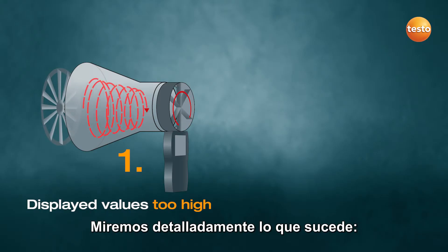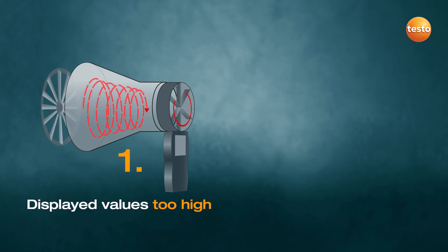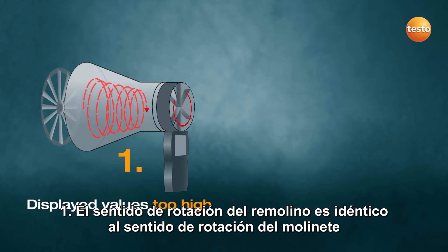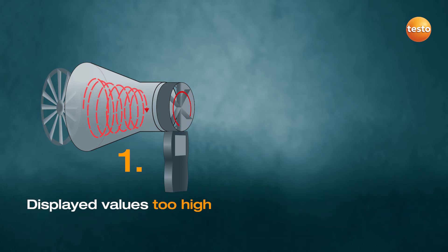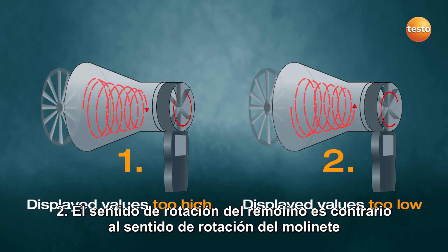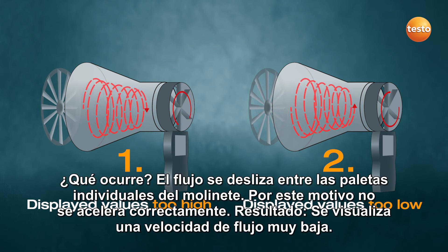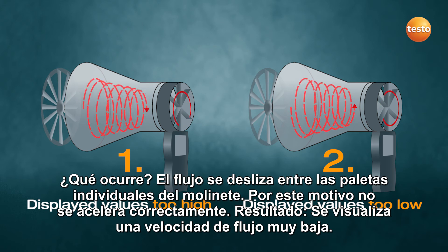Let's take a closer look at what happens. Case 1: The direction the swirl rotates is the same as that of the vane. The flow hits a larger cross-sectional area of the individual blades of the vane, making it accelerate too fast. Case 2: The direction the swirl rotates is opposite to that of the vane. The flow passes between the individual blades of the vane, meaning it doesn't accelerate properly. Result: an inadequate flow velocity is displayed.